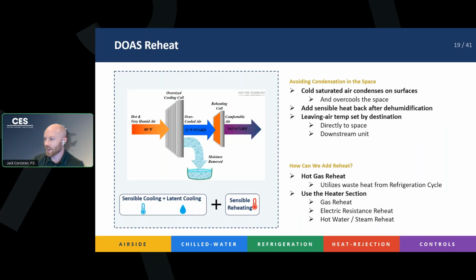We're going to move directly left and right. But as I said, we're not going to be delivering that cold sub dew point temperature air into the space, and there's no risk of condensation anymore. And essentially, this is very, very powerful if you're dumping the air directly into the space, because you wrung out all the moisture, and now you're delivering the air into the space at a neutral temperature that isn't going to cause an extra load in your space, right? You're delivering it neutrally into your 70-degree and 50% relative humidity room.